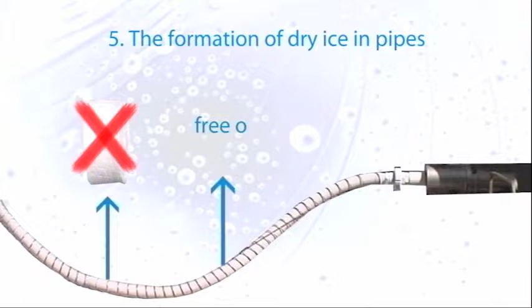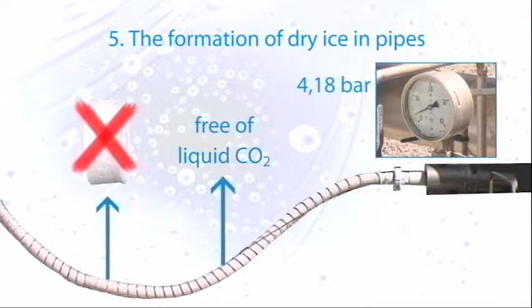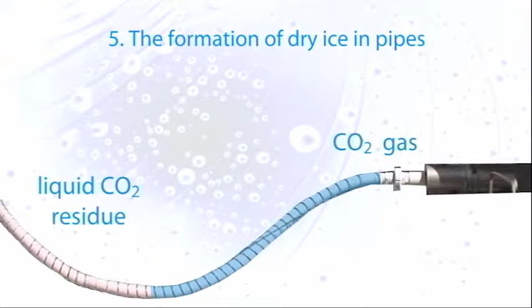To prevent this risk, hoses and pipes must be made free of liquid CO2 before the pressure is allowed to decrease below 4.18 bar. You can do this by sending CO2 gas through the tubing while the residue of the liquid CO2 comes out of the tubing at the other end.